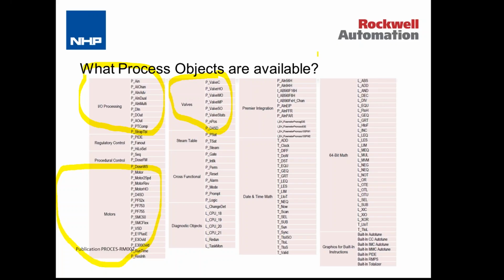Below that, steam tables, which are much more specialised. And then the section below that, which is referred to as cross-functional, you'll find a lot of these objects are actually embedded in the other three groups that I've just been through. Things like the interlocks, the permissives, the mode, the alarm. You'll find some of those are already embedded in the other objects, but they can be used in their own right in a standalone fashion as well. Below that, you will see that there's a group of diagnostic objects. So these are objects that allow us to monitor how the system is performing. So looking at the CPU loading, looking at redundant controllers, monitoring the task performance, so we can get a first-hand look at how the system is performing, once again from the HMI screen.